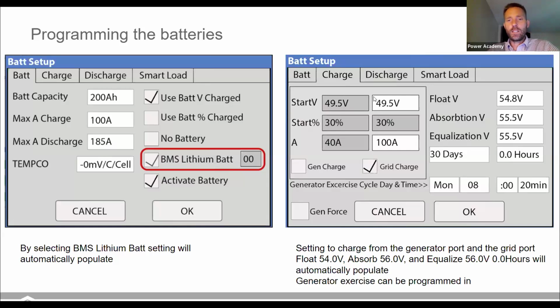On the battery setup side, under charging, you've got options for charging from a generator and options for charging from the grid. Think of this as the gen port, so if you've got AC coupled solar, you could be charging from that AC coupled solar. You can let it know what percentage to start charging at, if you've got battery percentage checked here. This will start up your generator if you've got a generator connected here. And you can set it to charge from the grid, and say when the battery drops below a 30% state of charge, it'll start a charging cycle from the grid.